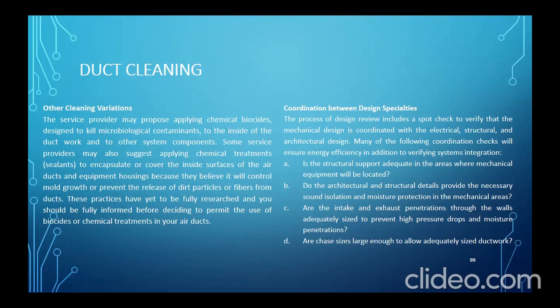Coordination between design specialties. The process of design review includes a spot check to verify that the mechanical design is coordinated with electrical, structural, and architectural design. Many of the following coordination checks will ensure energy efficiency in addition to verifying system integration. A. Is the structural support adequate in the areas where mechanical equipment will be located? B. Do the architectural and structural details provide the necessary sound isolation and moisture protection in the mechanical areas? C. Are the intake and exhaust penetrations through the walls adequately sized to prevent high pressure drop and moisture penetration? D. Are the chases large enough to allow adequate size ductwork?